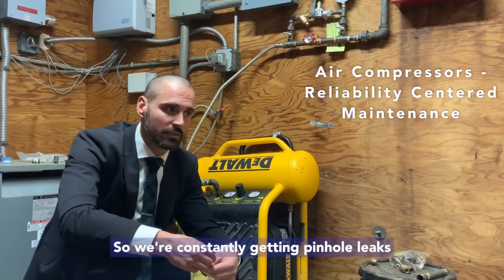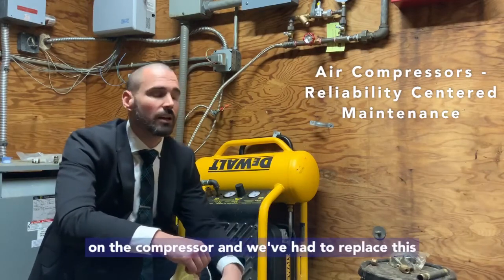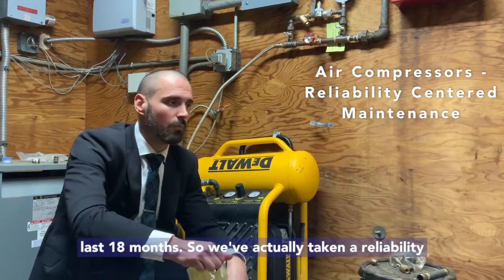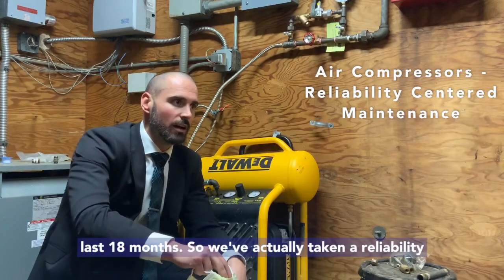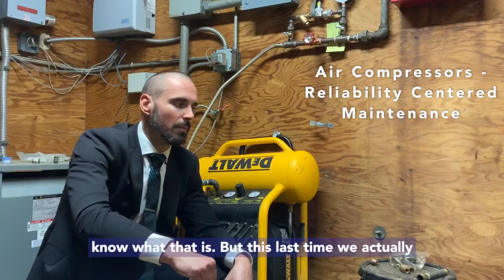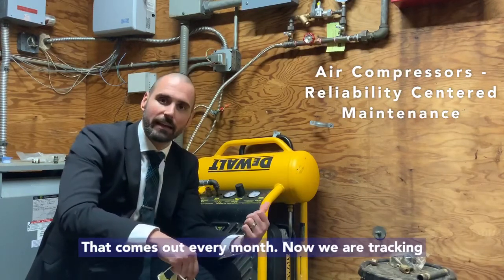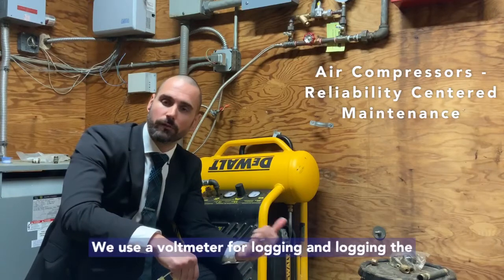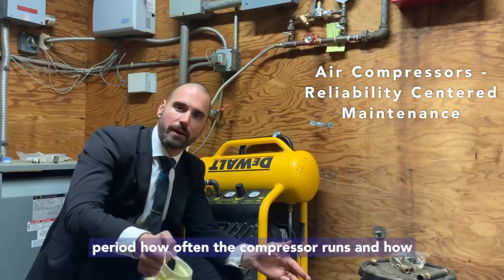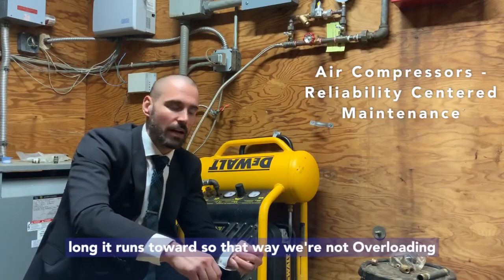We're constantly getting pinhole leaks, having to go out there and repair them, and those leaks put a lot of taxation on the compressor. We've had to replace this compressor four times in the last 18 months. So we've actually taken a reliability centered maintenance strategy — I'll post a link if you don't know what that is. This last time we put an asset tag on it and we have a PM that comes out every month. We're tracking how frequently the compressor is running using a voltmeter for logging the voltage, tracking once a month over a six-hour time period how often the compressor runs and how long it runs for, so we're not overloading the compressor.